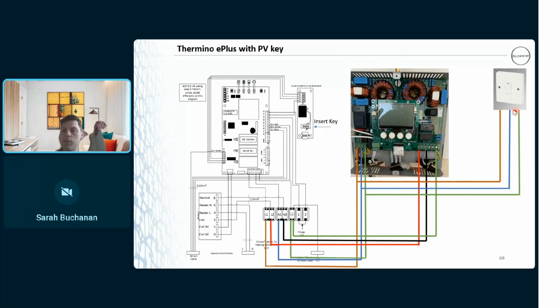So you've got your permanent supply coming in around there, into the incoming supply, the eddy, and then piggybacking off of that into your L1 and N1 and earth. So you just follow that back there. Your modulating live, your switch live, is fed from your output terminals here. If you just follow that, that's where you run them to their L2 and N2, and then obviously your earth.